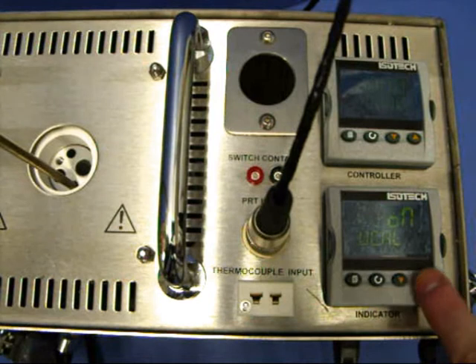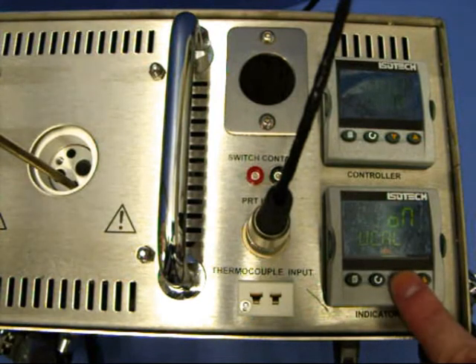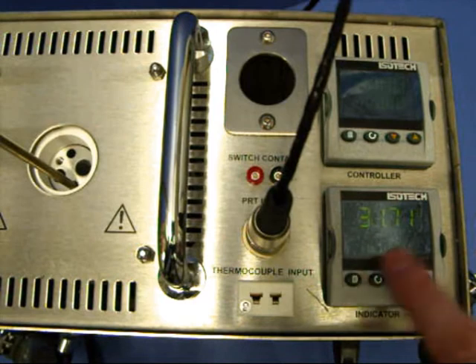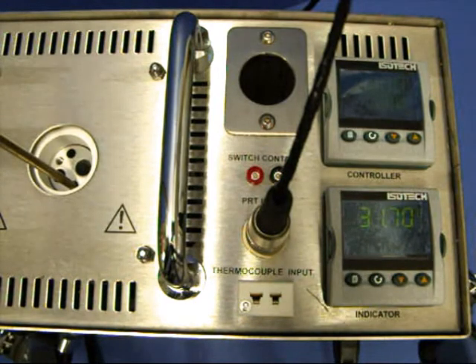When calibrating an unknown sensor against a calibrated probe it may be necessary to switch the calibration off for the unknown and on for the calibrated probe.